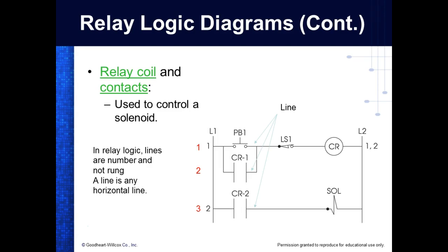On the right-hand side of L2, which this guy did incorrectly, we have numerical cross-referencing. This shows the location of the contacts being controlled by the relay. So this one's in rung 1, and I'd come over and find its contact, put line 2, then a comma, and a 3, indicating where the contact's at.